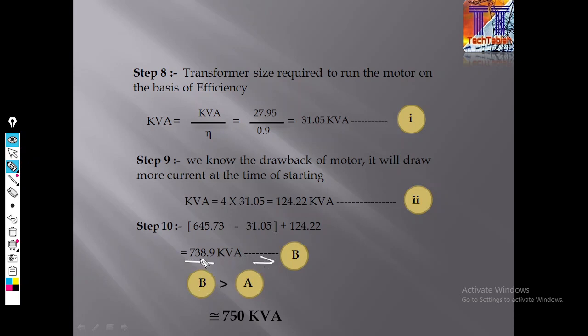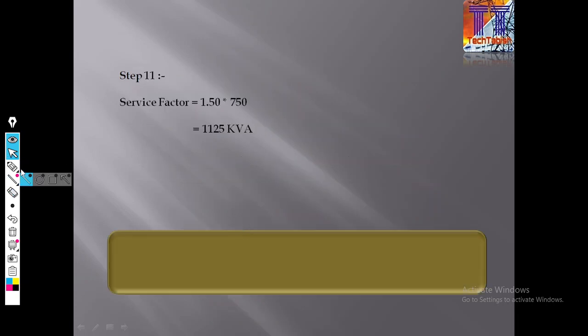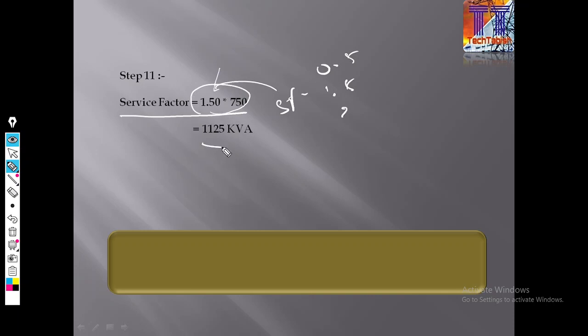If we compare 738.9 with 645.73, which we denoted with A, this is on the higher side. So the rating of the transformer is near 750 kVA. So this is higher, that's why B is greater than A. The nearby rating after calculating is 750 kVA, so we will select this transformer. After this, we will see the service factor. In every motor there is a service factor, denoted on the nameplate of the motor, such as 1.5 or 2. We have taken a 1.5 service factor, and after taking 1.5 we have to multiply this with 750, and it will come to 1125 kVA.